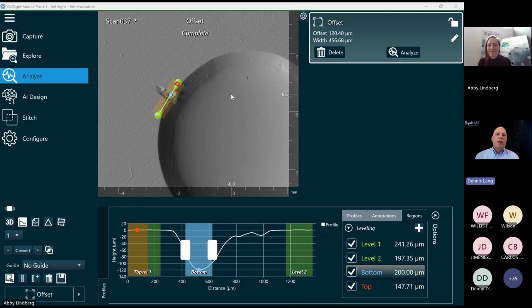And in the case of one company, they were receiving pitot tubes significantly outside of spec on the data sheet that their vendor was providing with the product. So they called the vendor up, and the vendor said, no, they're good. And they said, well, here's the GelSight PDF reports showing you they're not good. And of course, pitot tube is a very serious safety of flight component. And that particular situation really caught that they were being manufactured out of tolerance from the OEM of the pitot tubes being installed on aircraft, and those aircraft were being put out into the world.